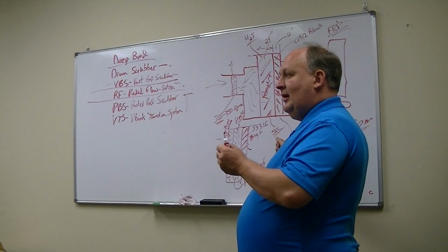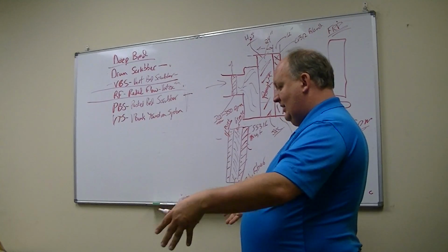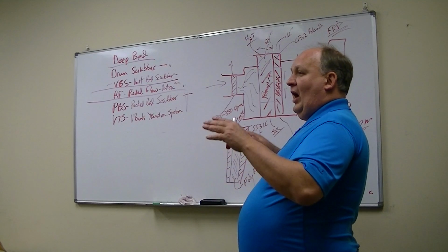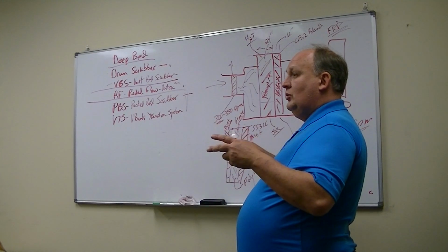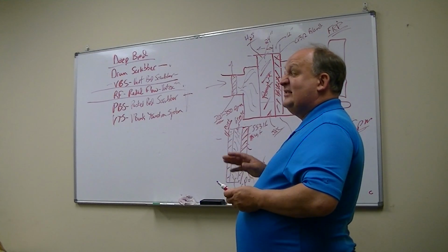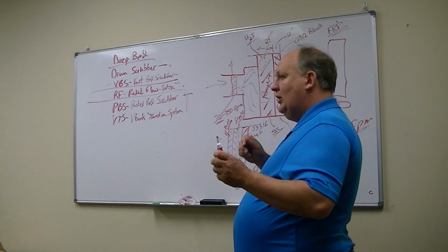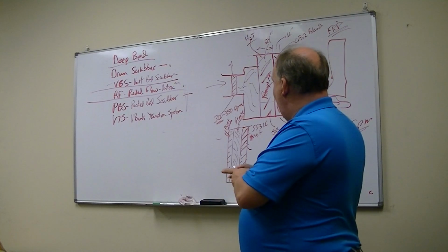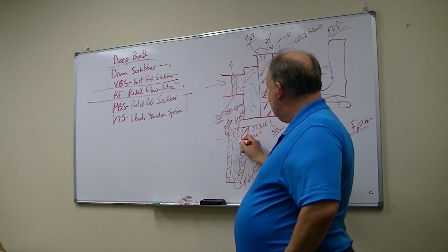But they should take the pad out, and they should stick it in some kind of a basin, some kind of a trough, with hot water with a degreaser in it, like Simple Green. Simple Green is a good, very available degreaser. And you let that thing soak in there overnight, because of all this grease in here.